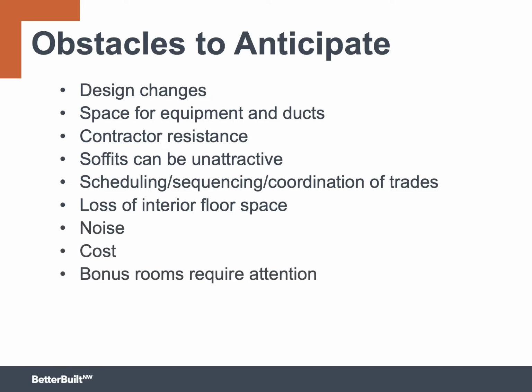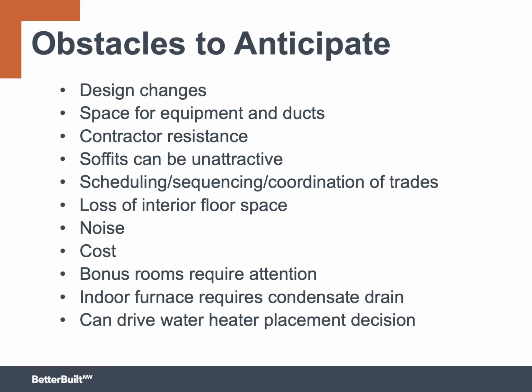There could be extra noise to deal with. There could be some cost complications. Sometimes bonus rooms are especially problematic and require special attention. The indoor furnace requires a condensate drain, and that needs to be anticipated. And finally, the location of the furnace can sometimes affect the location of the water heater because you want the same gas line to serve both devices. All of these challenges will be addressed as we move through the training program.